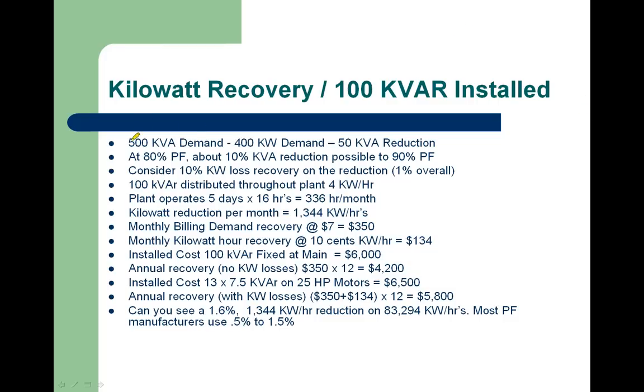We have a site here that has 500 kilowatt, or 500 kVA demand, with a 400 kilowatt demand. We have a power factor of 80%, and we're looking for a 50 kVA reduction, which would take their kVA down to 450, which would give them a 90% power factor. If we look at some potential kilowatt I²R loss recovery of 10% of the reduced kVA, and we're looking at 50, we could actually get down to about a 1% overall reduction in kilowatt hours. That's a possibility.